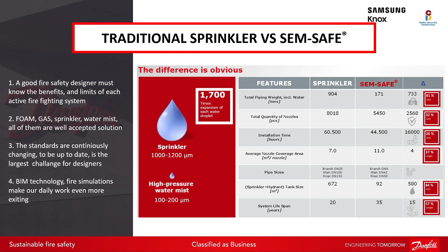This is just an extract of the result of this high-rise building. Investors are interested, it's not commercial talk, we can be cheaper - no, these are facts, open book. You could see the sprinkler design was ready at 904 tons of water and pipe for that high-rise in Cyprus, versus 171 tons with high pressure water mist.